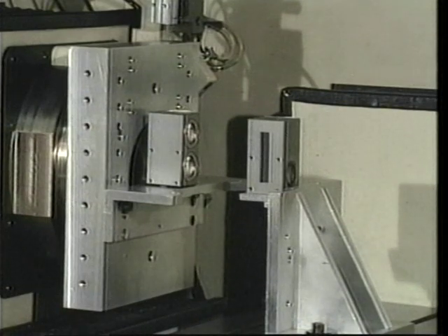To change the setup for pitch measurement, the reflector and interferometer would be reoriented vertically as shown. In this lab, we have demonstrated yaw measurement with an angular interferometer system. We have discussed how the angular interferometer and reflector use two measurement beams to sense the rotation of the moving reflector. We showed the setup of the hardware and discussed a method for data collection. Like straightness of motion data, yaw measurement data can be used to estimate workpiece errors as well as to provide data for error compensation routines.